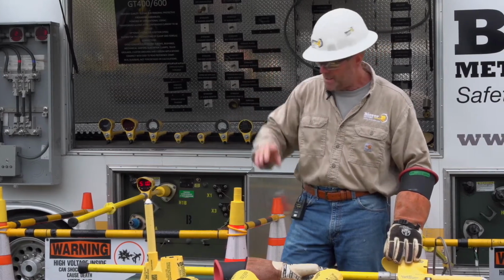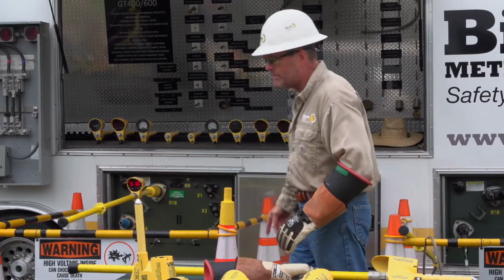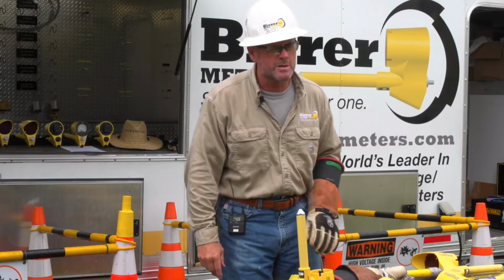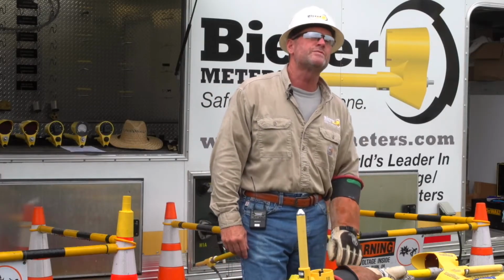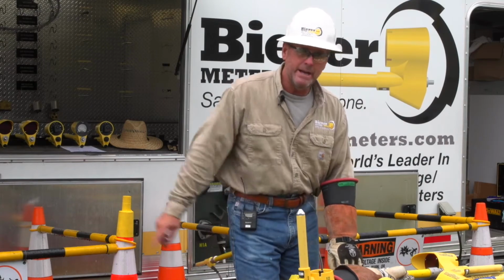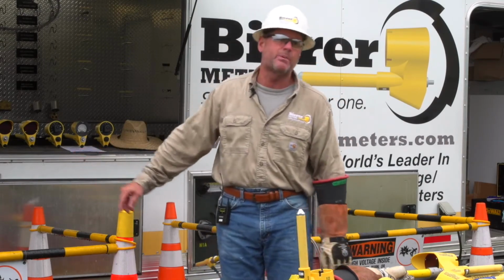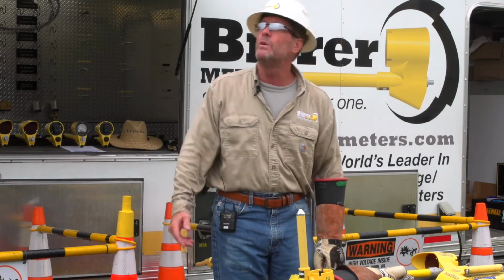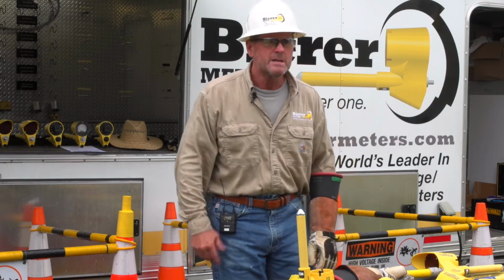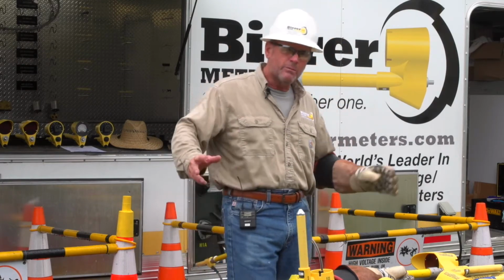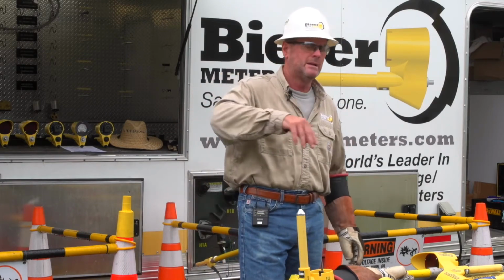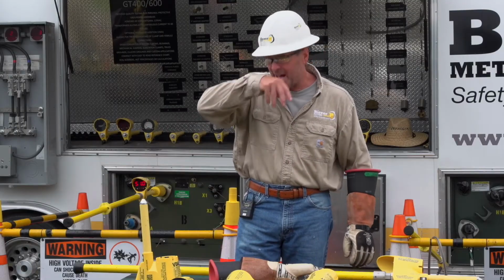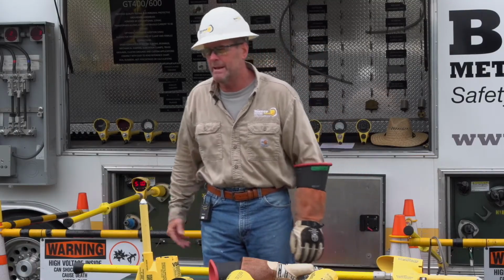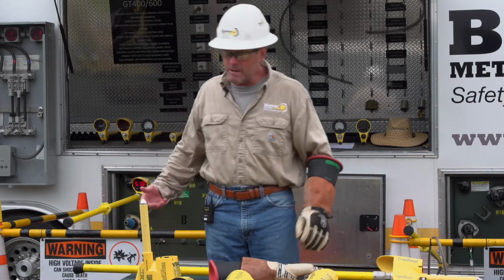So we do a test here. The reason we test on a live known voltage source is to verify our tool is functioning properly. And here, the tool is actually not functioning properly — we should be at 20,000 volts like we were this morning before the rain came. So we've got a little bit of an issue, and we're aware of it. It's not very accurate, so something's going on here that we should think about and talk about.